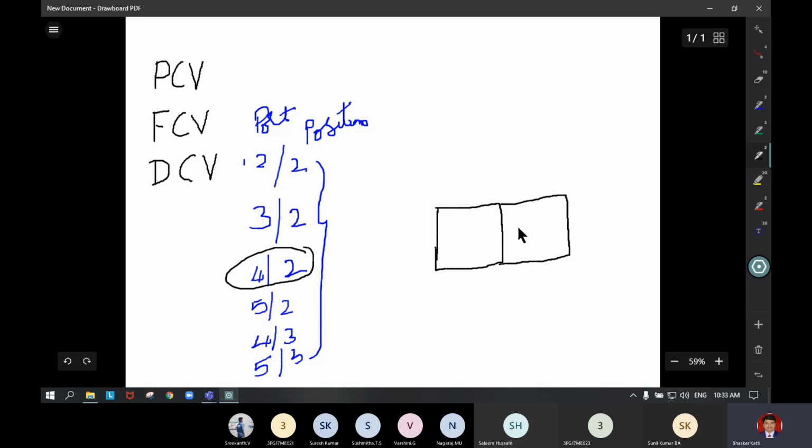So this represents the two positions, and always we have to write the port positions for only one box. So how many ports do we have to write? 4 ports. These 4 ports are the pressure port, that is the P line, the return line, that is the T port, and we have two working lines, A port and B port. So these are the port numbers.